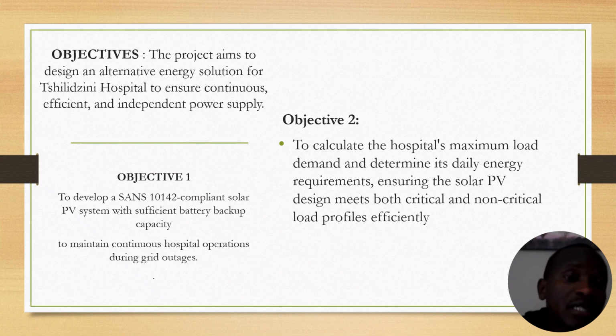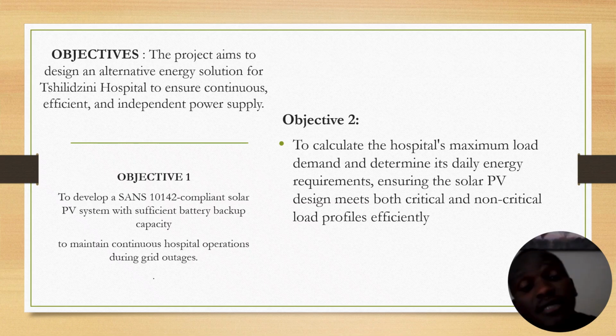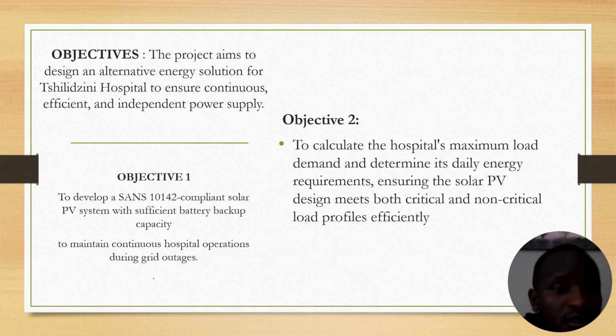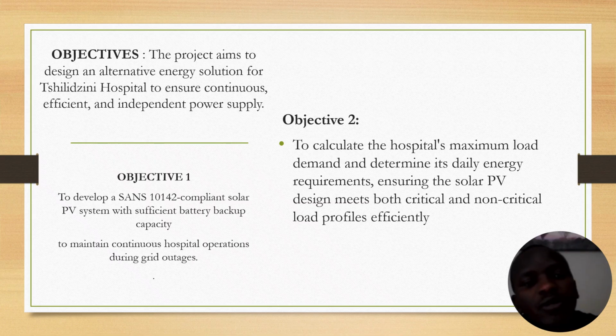These are my objectives. The project aims to design an alternative energy solution for Tshilidzini Hospital to ensure a continuous, efficient, independent power supply. Number one, to develop SANS 10142 compliant solar PV systems with sufficient battery backup capacity. This is the standard which you must comply with to maintain continuous hospital operations during grid outages.